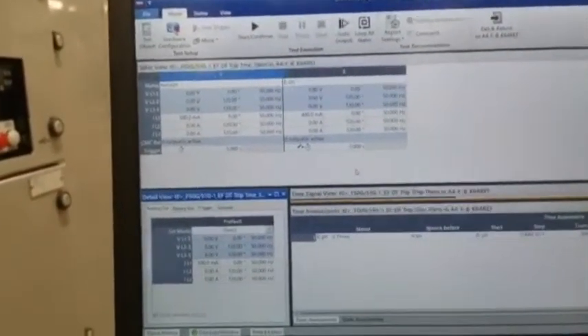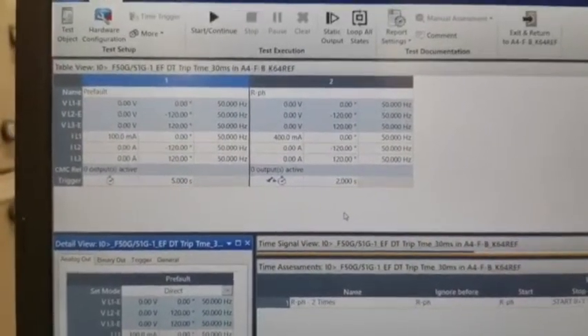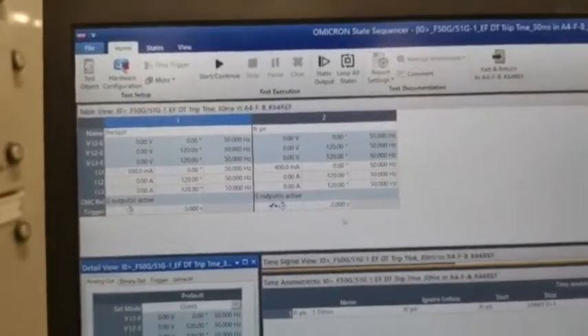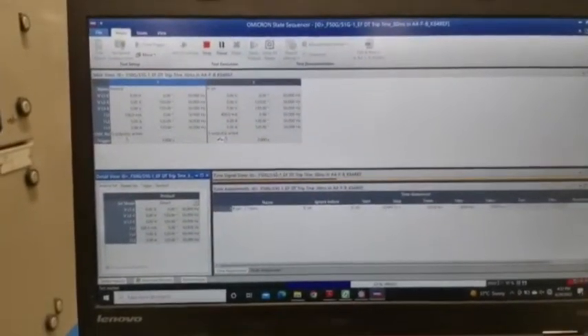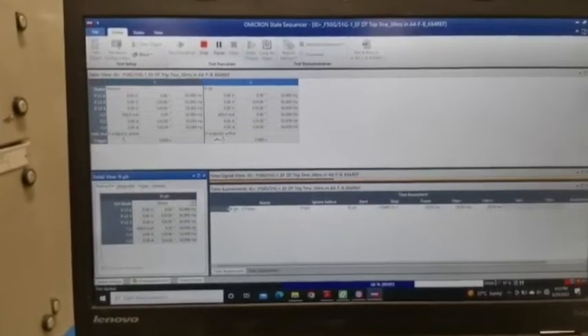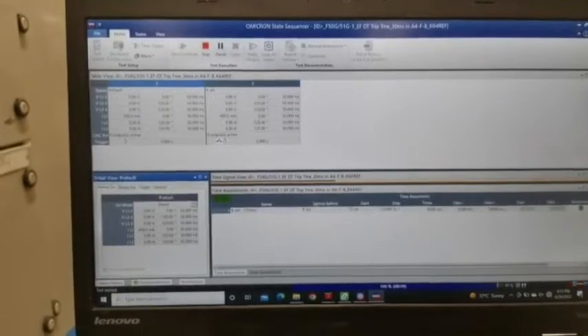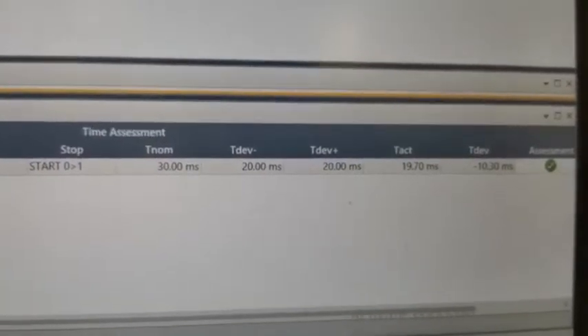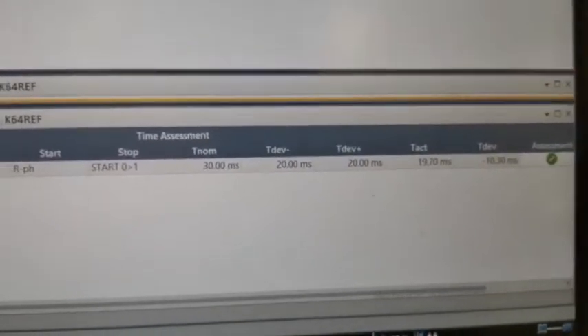Our setting is 200 milliamps, so now I am injecting two times the setting — 400 milliamps. The actual measured trip time is 19.70 milliseconds.